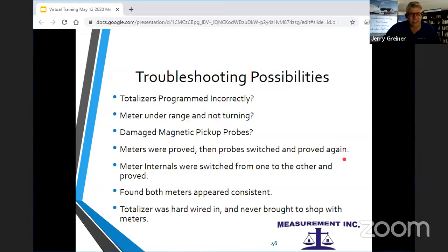They never went below 10 cubes a day. The one totalizer was the one that they would normally look at because it was at the end that they would hang out at, and they could see it would never drop below 10 a day. Usually it was 18 and sometimes go 10. And the 3/4 inch meters have a flow rate 10 is the minimum, so they were above the minimum. It should be working good.